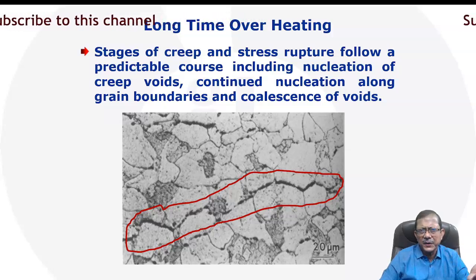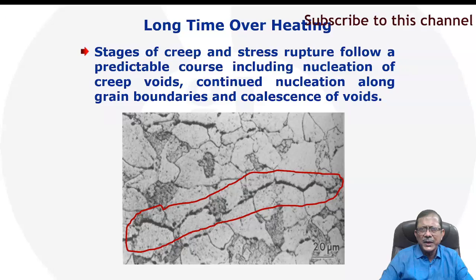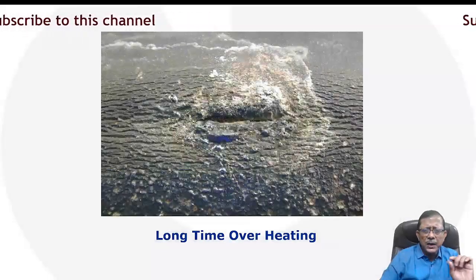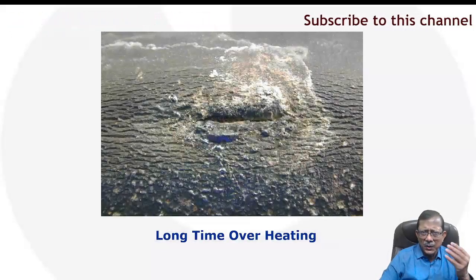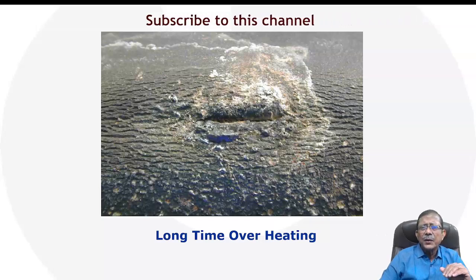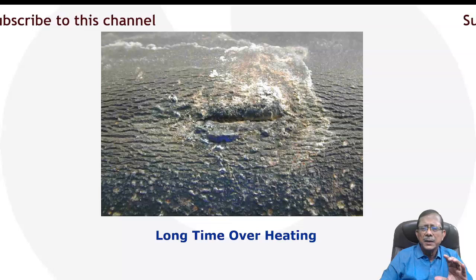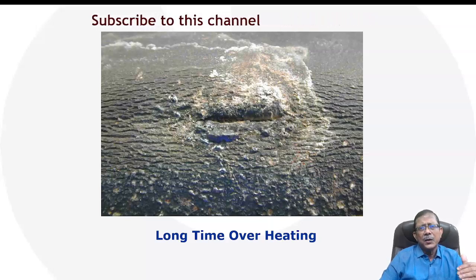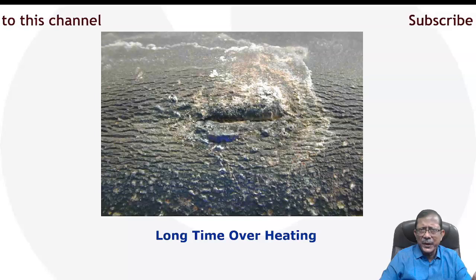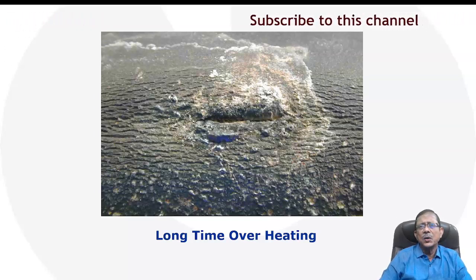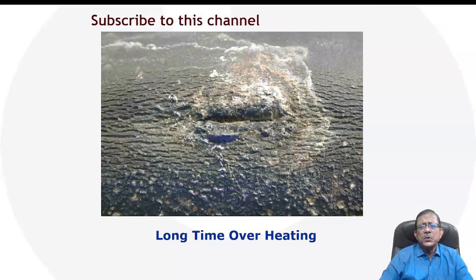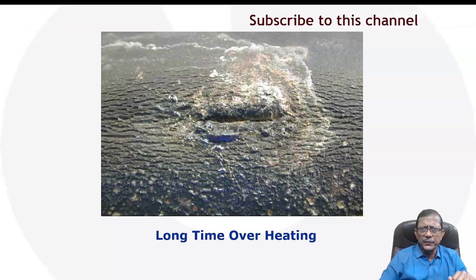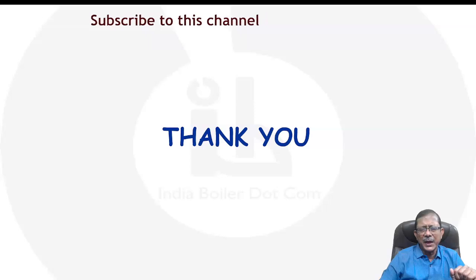Physically, the failed component may also show what is called an 'elephant hide' structure on the skin due to oxidation. That is what long-term overheating or creep failure looks like. Every boiler operation, inspection, or maintenance engineer must understand what causes creep — any component working in a creep regime temperature requires very careful attention. That will be all for today, thank you very much, bye.